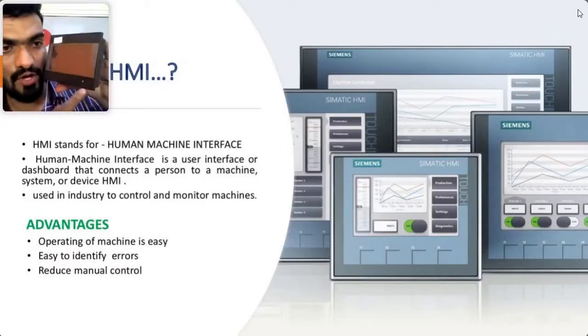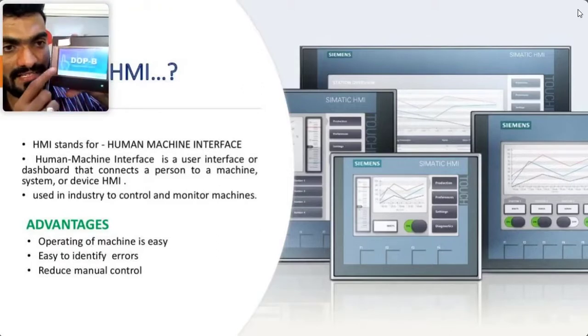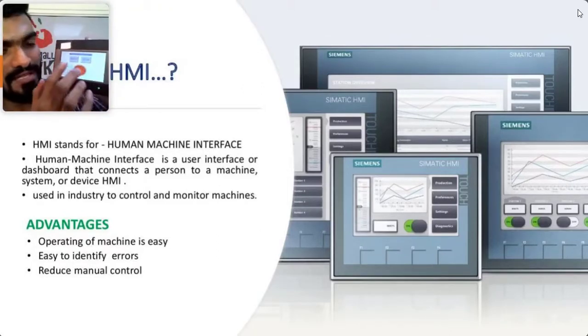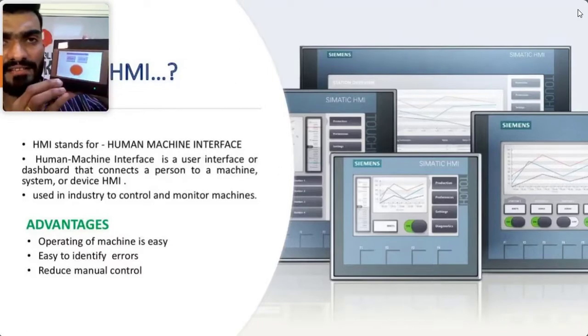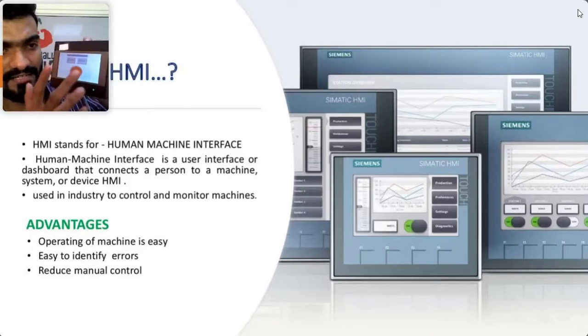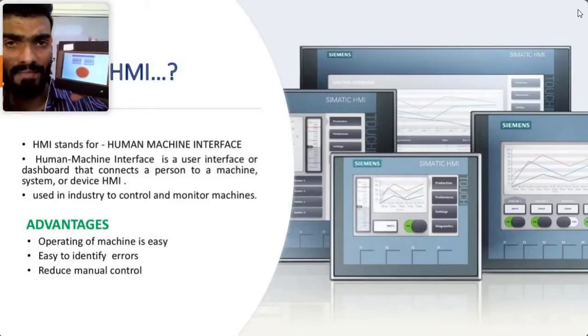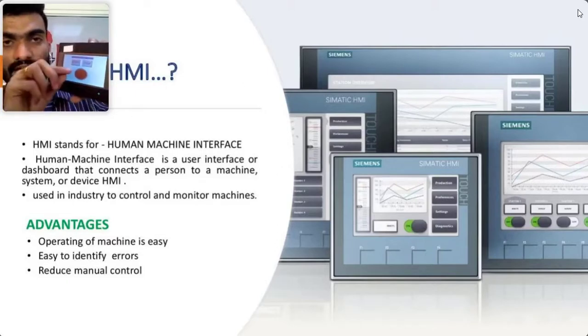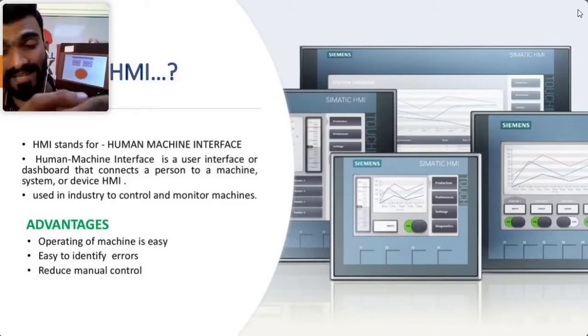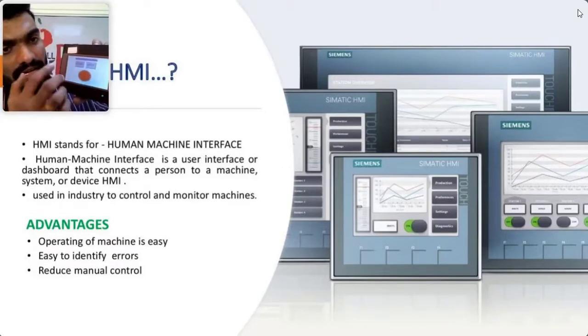So this is HMI, see how you will get a screen. We have designed a small screen here because in this HMI the advantage is anyone can design home screens and start-stop buttons, everything. It's all ready-made templates available in the software, so we just drag and drop, and we have to give addressing between the PLC and this HMI. Then the communication has to be established.